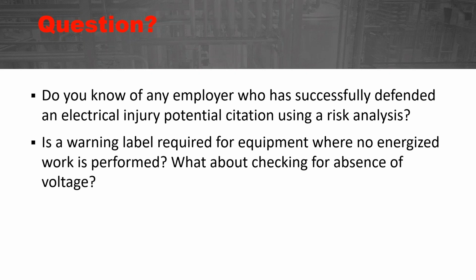They did a little bit of a risk analysis, but most of the time it is, did they follow the standards? Did the employer do what they were supposed to do in the standards? Do they have an appropriate electrical safety plan? And also, what did the worker do? Was he doing what he was supposed to be doing, or was he doing something that he wasn't supposed to be doing? And was he trained? So one of the key things besides just a risk analysis would be to get proper documentation, such as electrical work permits and training of the employees, and a potential arc flash study, and giving them the PPE that is required, and make sure that you're on board with what they were doing. So there's a number of things that go into successfully defending either a citation or a lawsuit, and a risk analysis is one of them.